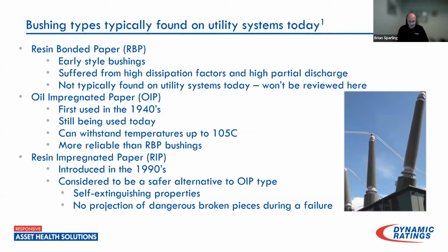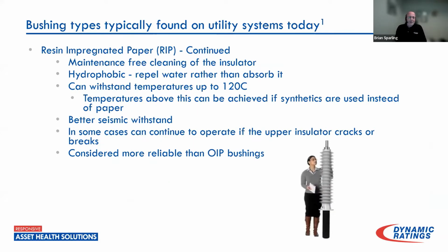The good news is when they fail, they don't explode, but the point is, nonetheless, they still do fail. And with these types of bushings, it's more or less maintenance free. They're not porcelain shell on the outside. It's a resin. It can sustain temperatures up to 120 degrees C, and it has a much better seismic withstand capability than porcelain bushings. So in some cases, they're considered more reliable than OIP bushings. That comes at a cost, and there are different operating characteristics associated with these types of bushings that need to be taken care of.